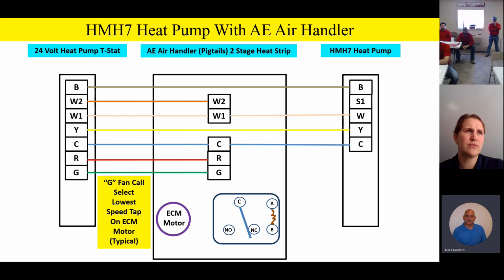Typically, and if you want to select a different speed tap on that motor, you can, but typically G is going to be hooked up to the lowest speed tap. That way, if the homeowner decides to have air circulating in the house all the time, they just turn the fan to the on position on the thermostat sub-base assembly, and it brings the fan on low speed just for air circulation. That's typically how we see that hooked up.